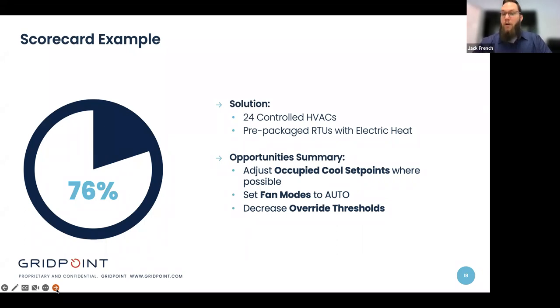And it all depends on what your goals are. So it's important to align what you want your scorecard to be with what your goals are. Next, set fan modes to auto. We talked about 79% of the units having their fan modes in auto, and 21% did not during the occupied hours. So do we have opportunities to set some of those fans to auto mode? That'll prevent additional baseload for those HVAC units, reduce the runtime of the fan, and help to lengthen the lifespan of that equipment.